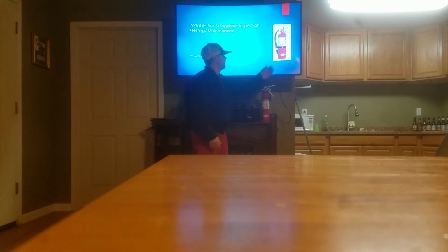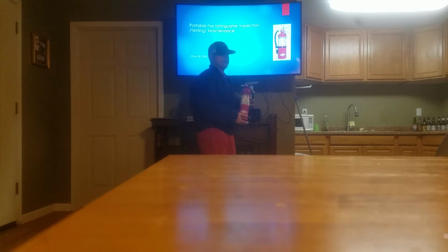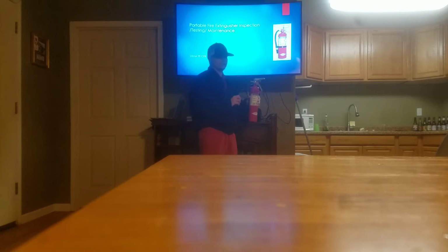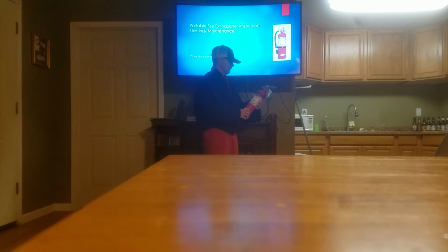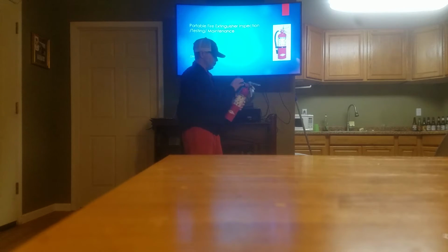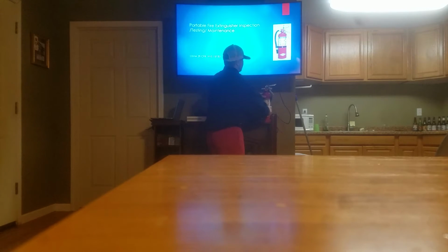And as you see right here, it's a picture of a portable fire extinguisher. Very similar to what I have here. The only difference is I used this in a previous training that I had conducted, and this one does not have the hose connected to it. So as you will learn later, this one would actually fail inspection. You would want to document that it does not have the hose connected to it, as it does in this picture right here.